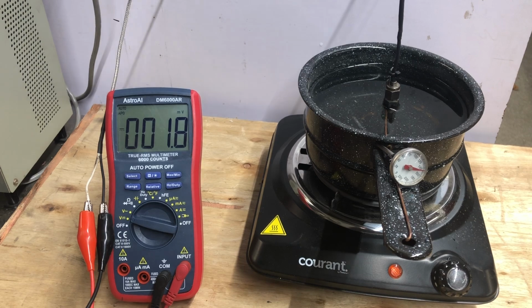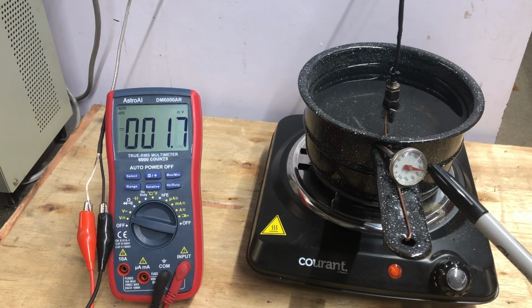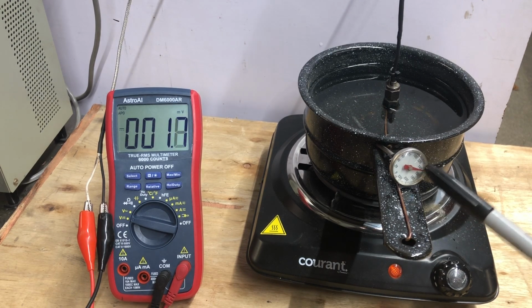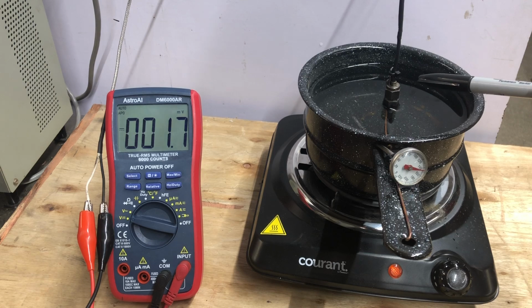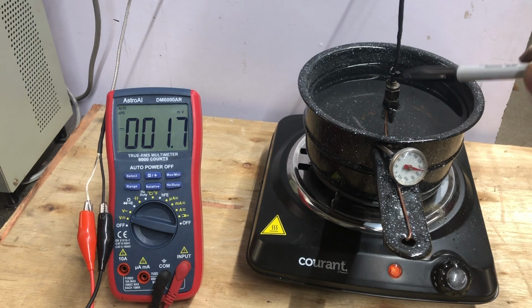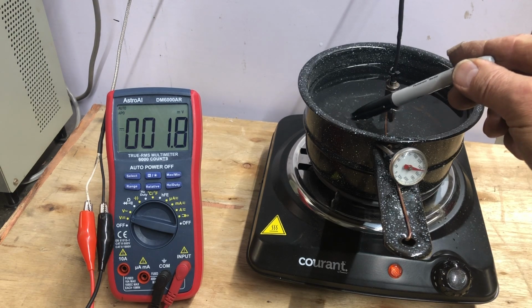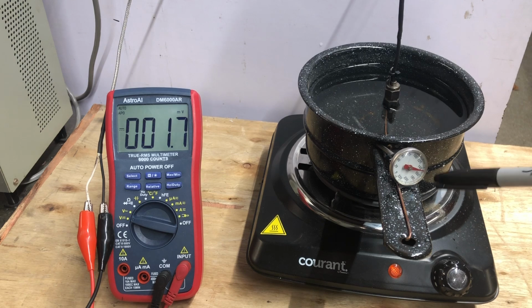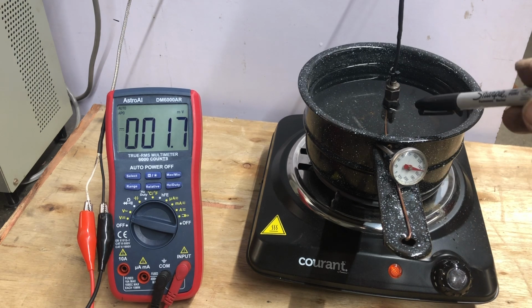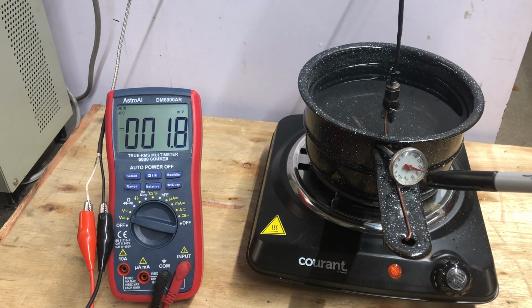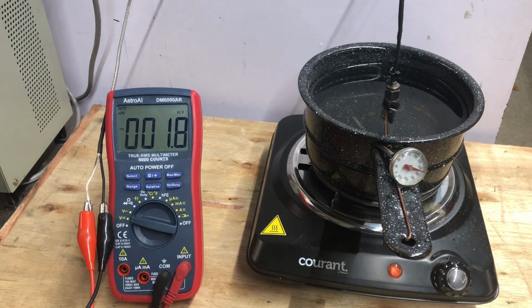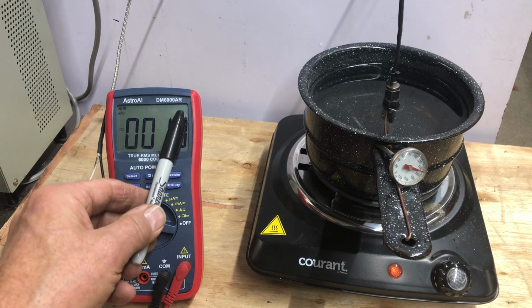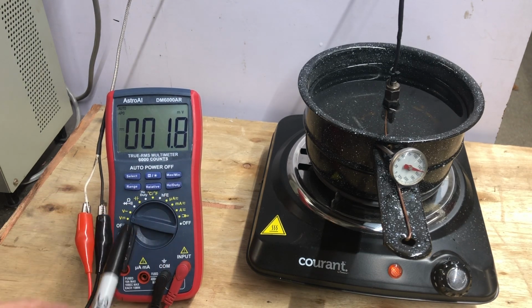So here's my test rig here. I have a thermometer in the water, and again, the probe is about halfway. It's not touching the bottom. It's about halfway down in the water. The same with the thermometer tip. I want an accurate reading of the temperature at the tip of my probe. I'm at about 150 almost, and as you can see, I'm in millivolt scale here, 1.8 millivolts.